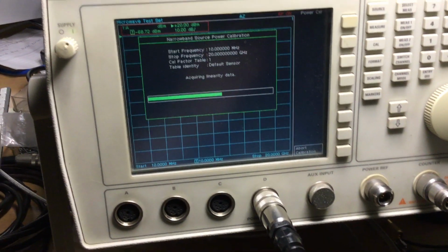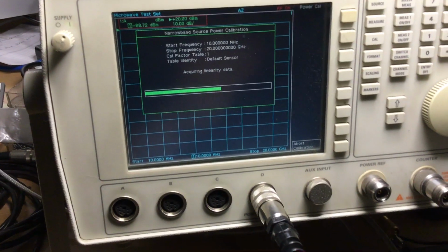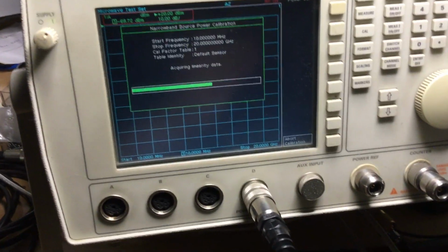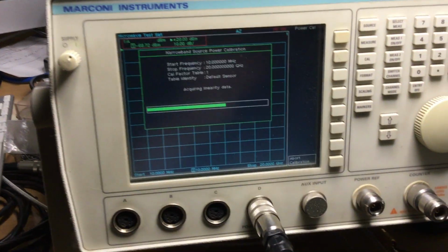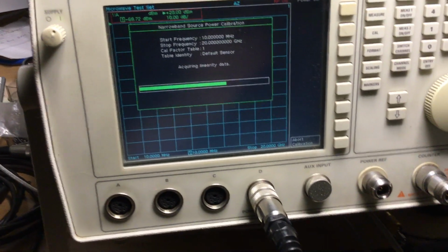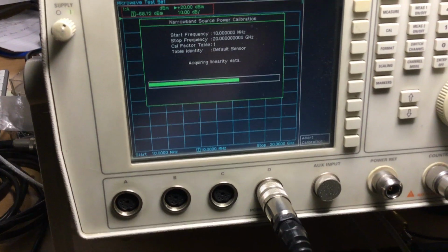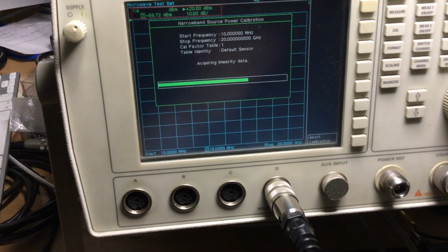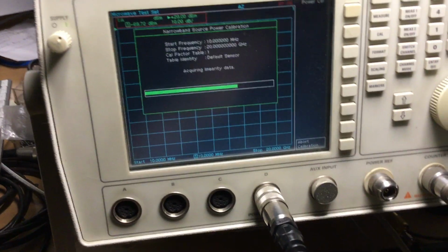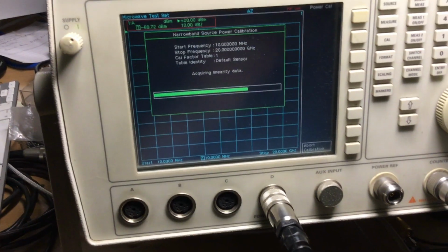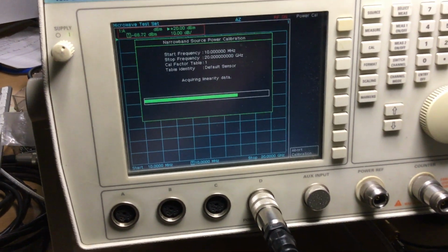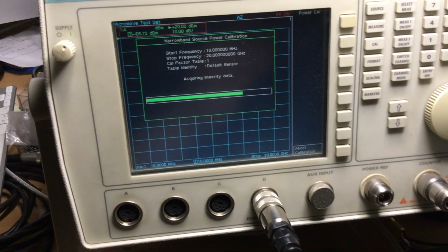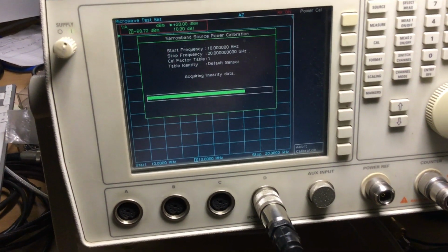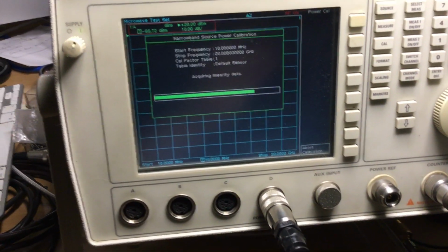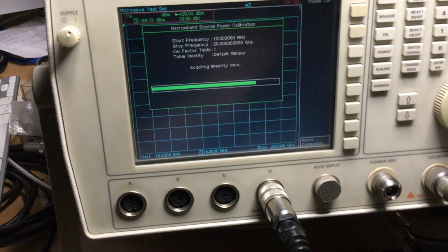linearity reading now. As you can see on the front there, it says Cal Factor Table 1. That's the table that we edit within the test set configuration with the table that's printed on the back of the sensor. And so that linearity, calibration factor, all the parameters of the sensor are entered into the test set memory first, so that when we do the calibration, it's using accurate parameters from the sensor, so it gives a better reading on the output that's aligned with what it should be doing. So we're ruling out any variances in the calibration side of things. We get that right first, get your standards and your references set properly, and then we can do the proper calibration. So we're nearing the end of this routine.